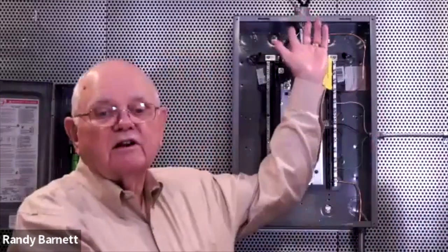Oh, so if I am tapping off of a larger conductor, 240.21, this is the rule that tells me 215.15 says I have to have barriers in this panel. It says, or if I'm tapping off of transformer secondary conductors, in other words, if these are the transformer secondary conductors coming in, then I would be required to have those barriers in place. And that's according to 215.15.